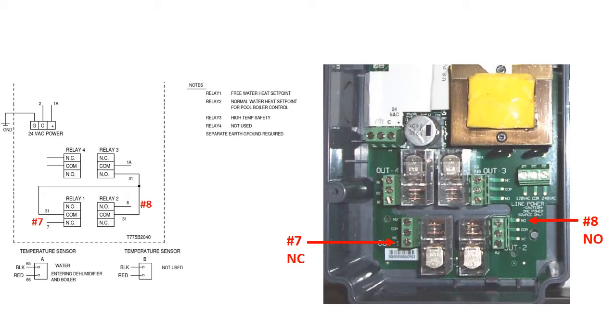Relay number 3 functions as a high limit and provides power to the other relays until its set point is reached, at which time it will de-energize and remove all power to the other outputs.